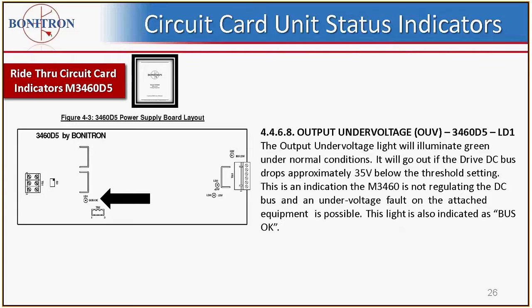This tells you that the ride-through is just not riding through or boosting. It's not regulating the DC bus, and an undervoltage fault on the attached equipment is possible. So in other words, if it's not boosting, you're going to see an undervoltage fault on the VFD. This light is labeled on the circuit board as bus OK.